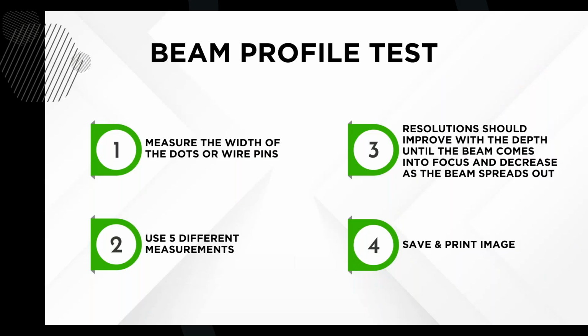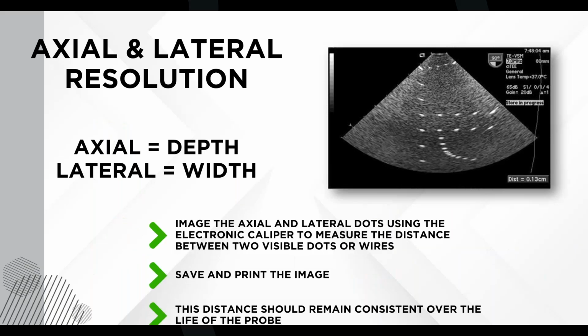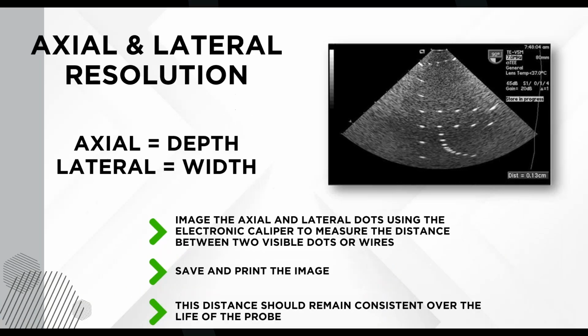Next test we have is axial and lateral resolution test. For the axial and lateral resolutions, we're going to hit this axial and lateral dots, wire dots right here on the left. They're going to take a measurement between the 2 of the smallest ones that you could see. You're going to image the axial and lateral dots using electronic calipers to measure the distance between 2 visible dots or wires. Save and print the image. This distance should remain consistent over the lifetime of the probe.